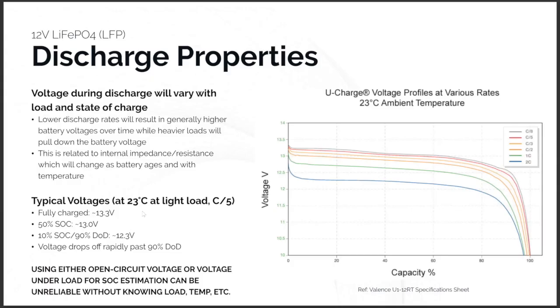Then on the other side, discharge. The key takeaway I want to show here is that, like with any battery, the lower the discharge rate, meaning how much current you're trying to draw from it, will generally have higher battery voltage, whereas heavier loads will pull down the battery voltage. That has to do with the internal impedance or resistance, which changes as the battery ages, and changes with temperature.